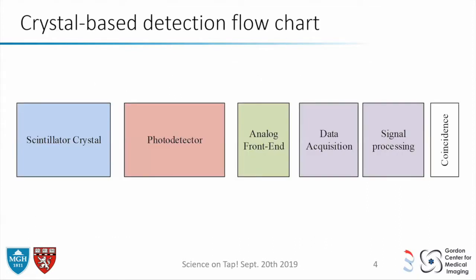So how does a scanner work? There's a basic detection chain that starts from a scintillating crystal in most systems. When it absorbs the gamma, it emits light. Then you have a photodetector, some analog front-end electronics, and then digital electronics for data acquisition. You can do signal processing to improve performance, then send it out, make the pairs, and it goes to the reconstruction engine.